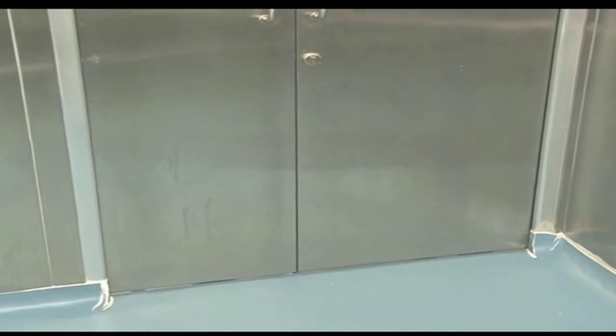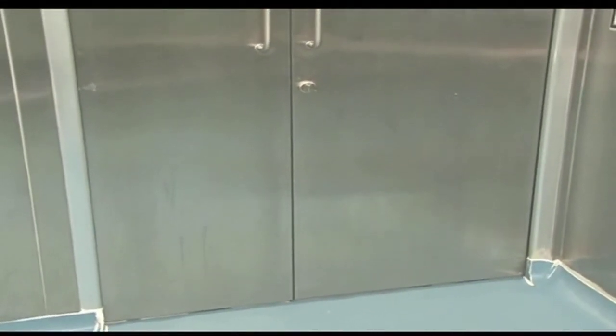The doors in the modular operating theatre are used to maintain the correct air pressure in the room. The door frame is made out of high-quality anodized aluminium extrusion, and the door panel is made out of compact laminated board that can withstand high abrasions.